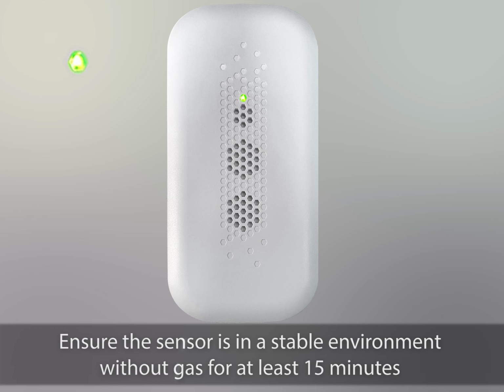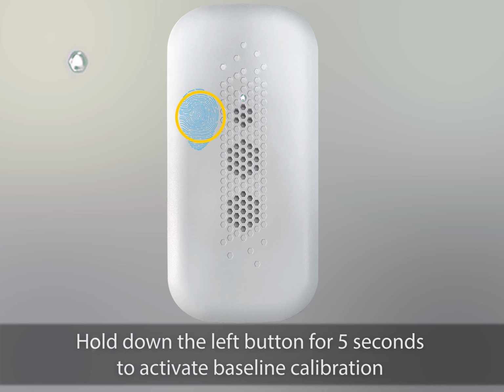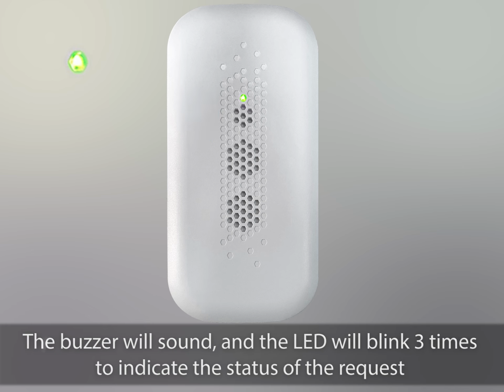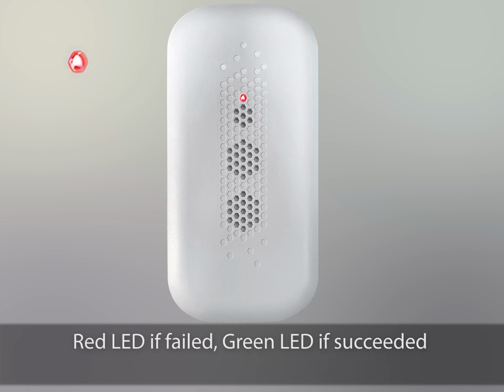To do this, you need to make sure the sensor is in a stable environment, without gas for at least 15 minutes. Hold down the left touch zone for 5 seconds to activate baseline calibration. The buzzer will sound and the LED will blink 3 times to indicate the status of the request. Red LED if failed, green LED if succeeded.